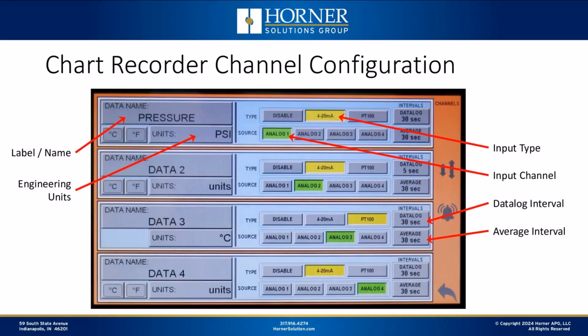And then you can also configure how frequently am I going to data log that particular analog input to the memory card. How often am I going to sample it? Every 30 seconds, every minute, every 5 minutes, whatever makes sense for your particular process. And then how often am I going to recalculate the average? You can also configure that as well. Okay, so that's your channel configuration.